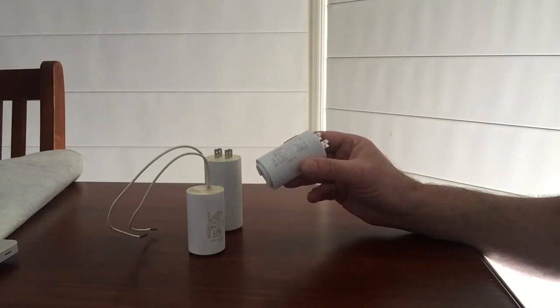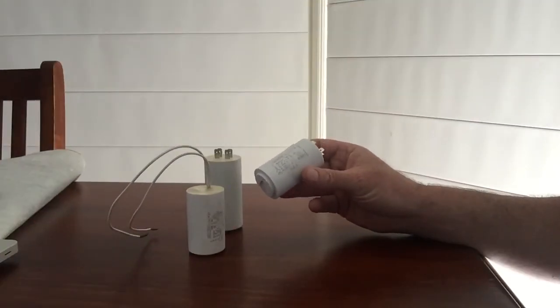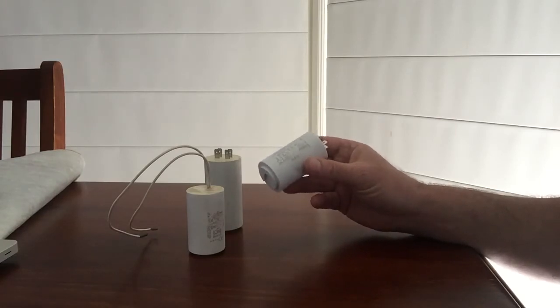Most capacitors in pool pumps these days are rated at a high voltage, around 400 to 440 volts. You might ask, but my supply voltage is only 240 volts, why are they rated so high? It's because of the induced voltages from the motor windings in the electric motor.